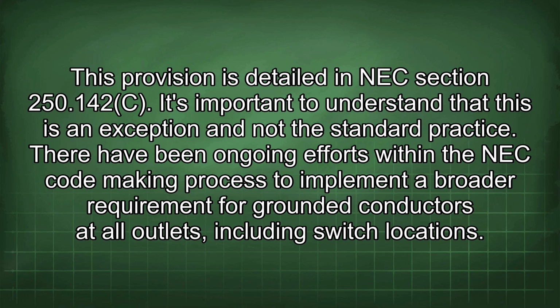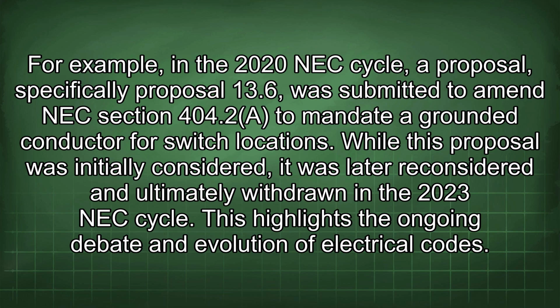There have been ongoing efforts within the NEC code-making process to implement a broader requirement for grounded conductors at all outlets, including switch locations. For example, in the 2020 NEC cycle, a proposal, specifically Proposal 13.6, was submitted to amend NEC Section 404.2 to mandate a grounded conductor for switch locations. While this proposal was initially considered, it was later reconsidered and ultimately withdrawn in the 2023 NEC cycle. This highlights the ongoing debate and evolution of electrical codes.